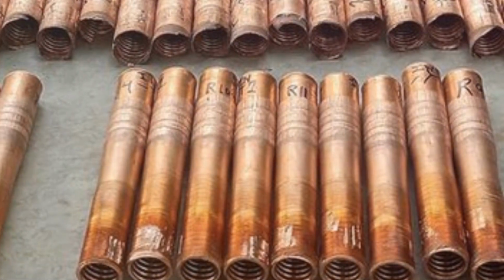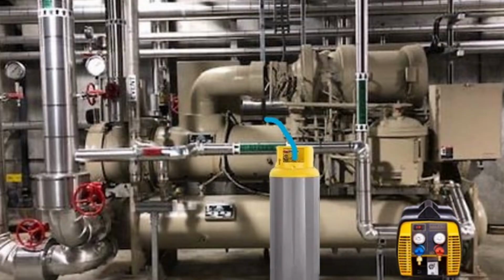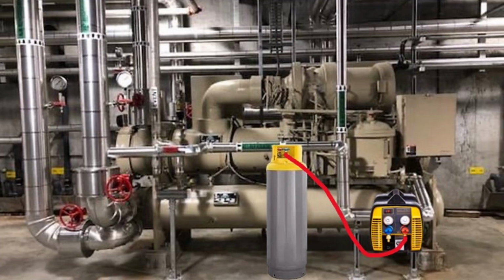After you have verified that you have achieved 40 degrees saturated on your entire machine, you'll push-pull the liquid refrigerant back into the machine opposite of the way you took it out. You will take the discharge of your recovery machine and connect it to the vapor port on your tank. Next, you will take the inlet of your recovery machine from the top of the evaporator and the liquid outlet of your tank to the bottom of the condenser. After you have push-pulled all of the refrigerant back into the machine, then pull the rest of the vapor from the tanks and you're all set.